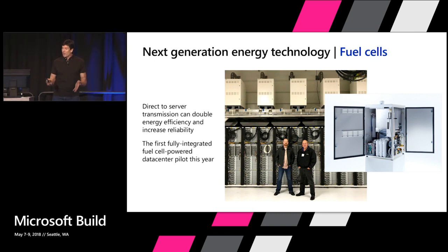As you know, data centers are powered by utility energy, utility electricity that comes into those data centers. And one of the things we realized as we looked at that architecture, first of all, utility power is not that reliable. So we have to have generators there to back up the utility power. But second, there's a whole lot of switches and transformers on the way from utility power into the data centers, into the servers. So every time you go through one of those devices, you lose a little bit of energy in the transition. So there's a significant amount of energy loss as you get down to the servers. And there's also, for any one of those switches, another potential single point of failure on the way to the servers.